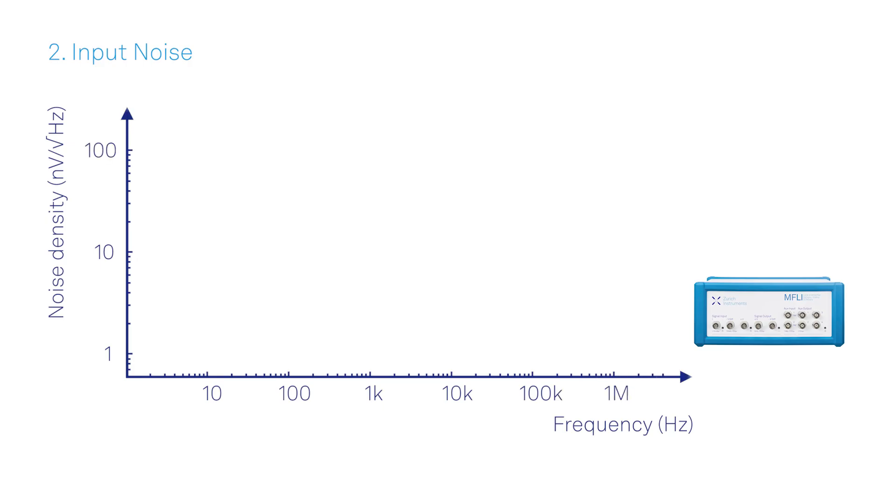Now let's take a look at the instrument's input noise. It needs to be low to measure small signals with a high signal-to-noise ratio. Manufacturers characterize the voltage noise density versus frequency. It can be as low as 2.5 nV per square root hertz, as in this example.